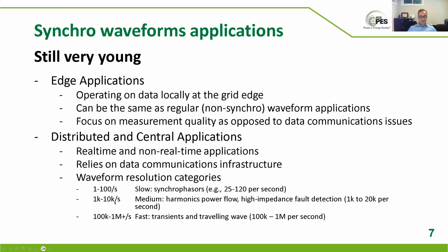Then you have the typical, medium sampling rate, from 1 kilohertz, maybe some older relays, to 10, 20, 30 kilohertz. So these are better quality, higher sampling rate relays, power quality meters, good quality meters and recorders, and they can help with harmonic power flow, high impedance fault location, things of that kind. And then you have some waveforms that you can take to 100 kilohertz to megahertz, assuming also the instrument transformer has the bandwidth to show faster events. That's the category of faster sampled waveforms, and these help with transients, traveling wave, fault location, things of that kind, even resonances in the circuits in the substation.